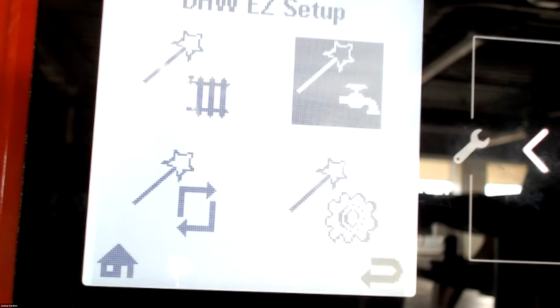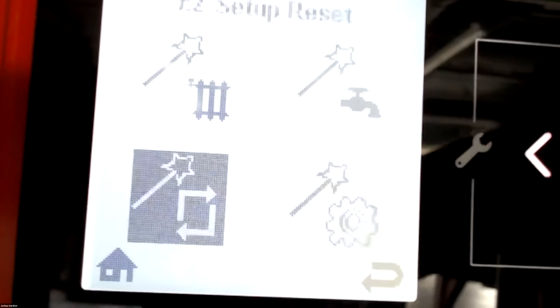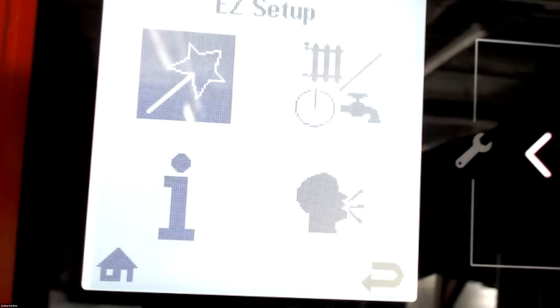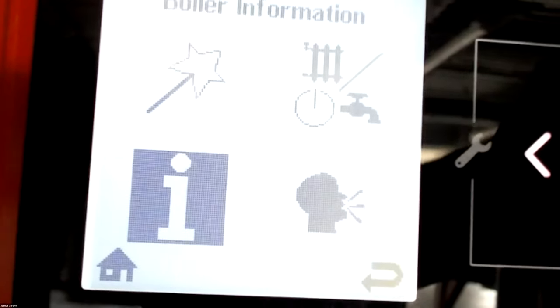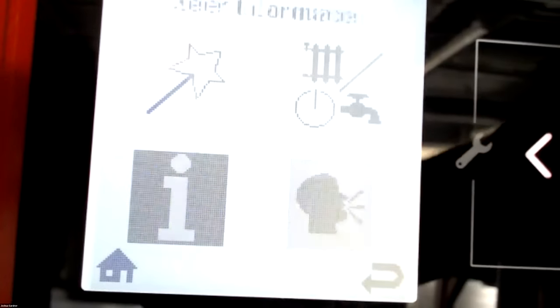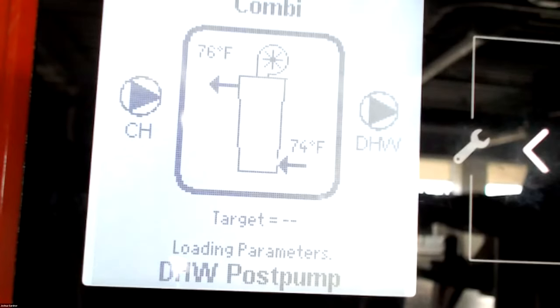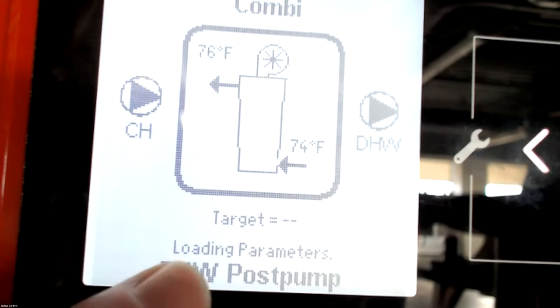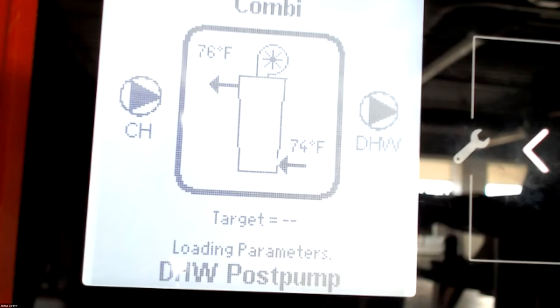And then we'd set a tank set point, where we want the tank set and what we want our boiler operating at. So we'd set, say, I want my tank set at 140 if I'm using the sensor. And then you would tell it, okay, what boiler temperature do I want to run when that calls? Do I want to run 180, 170? So you have the flexibility to adjust that as well. And that is our basic functions on this control. So if we go back to the home screen, you can see the adjustments, it always says loading parameters at the bottom. So we can wait for that to load.